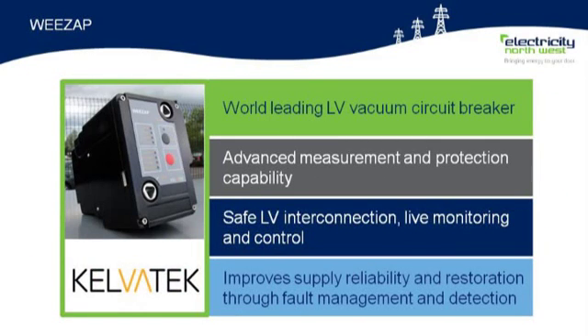The device you can see here is a WEEZAP. We'll be fitting these on the LV circuits at the distribution substation. These will replace the traditional fuse unit, and it offers three enhancements. One is control of the circuit. Two is the visibility of our LV network through the monitoring capabilities. And three is the advanced fault detection, which allows us to monitor faults on the circuit and react to them a lot more quickly, and also be proactive in tackling them. They can sometimes detect faults that haven't gone permanent on our circuit before customers go off supply, so this improves our service to our customers and our restoration.